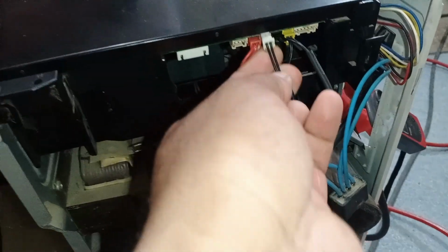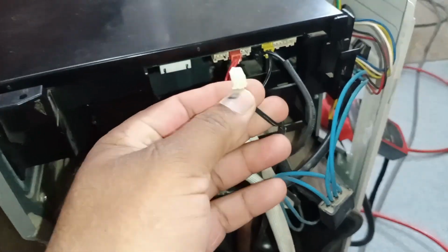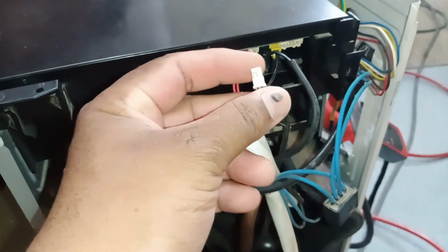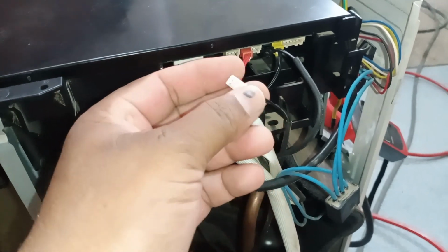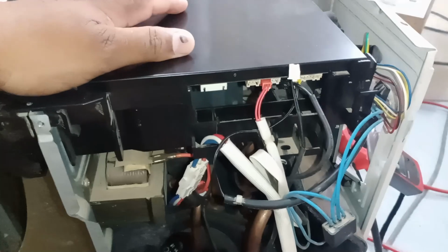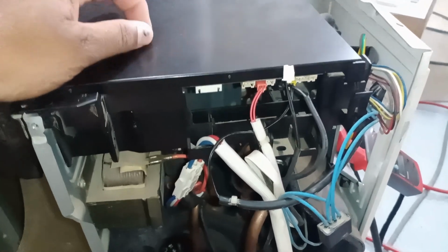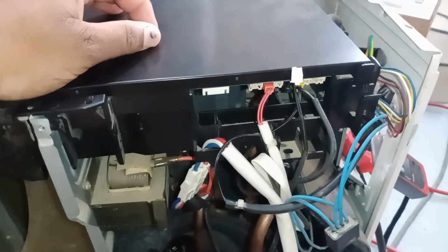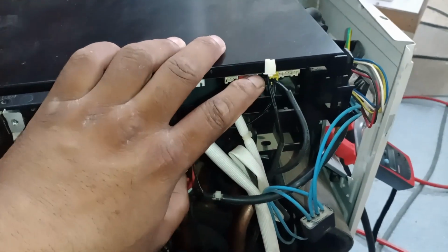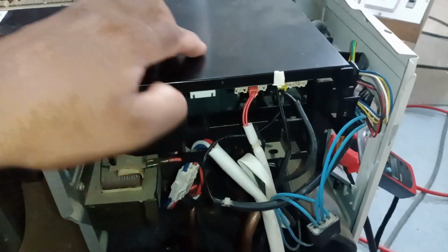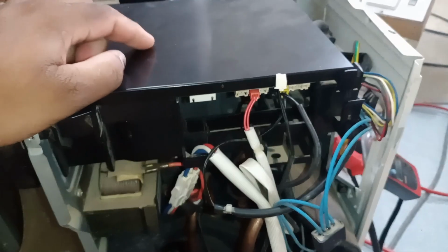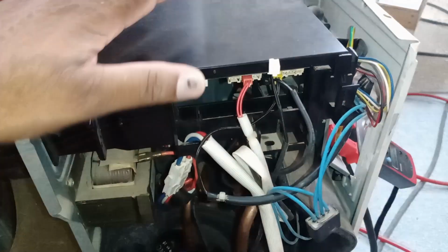Look at this white connector. This is for the discharge pipe sensor. If this connector gets damaged or has a loose connection, the system will display error code 2. Additionally, if the PCB itself is faulty, you will also get error 2 because the PCB supplies 5 volts to the sensor, which is essential for feedback to the microcontroller. If these 5 volts are missing, you will need to repair the PCB to resolve the issue.